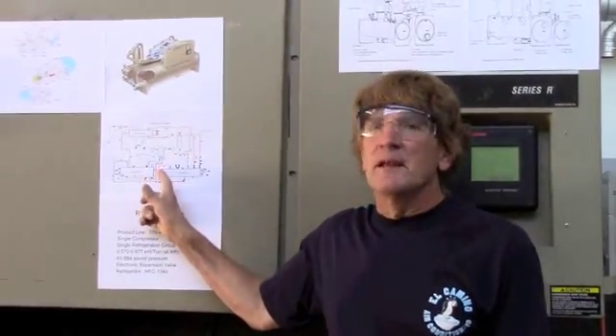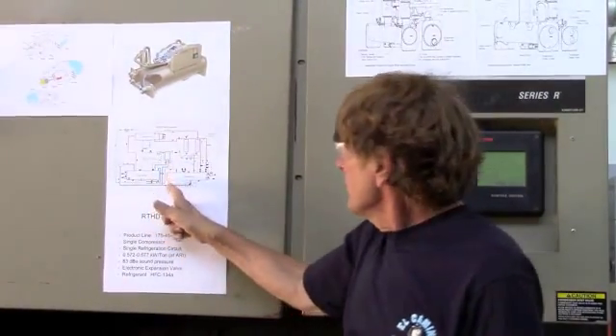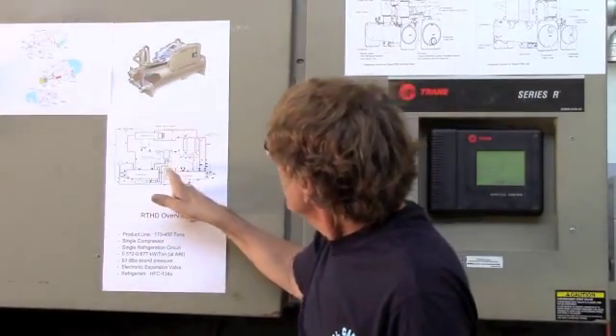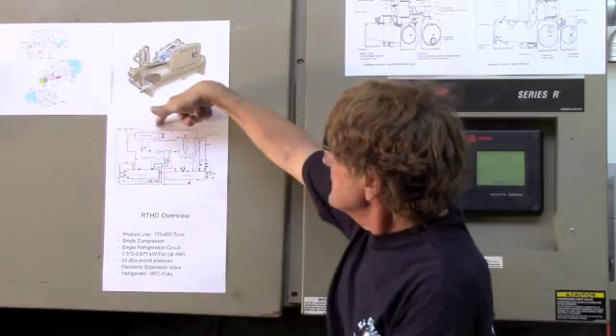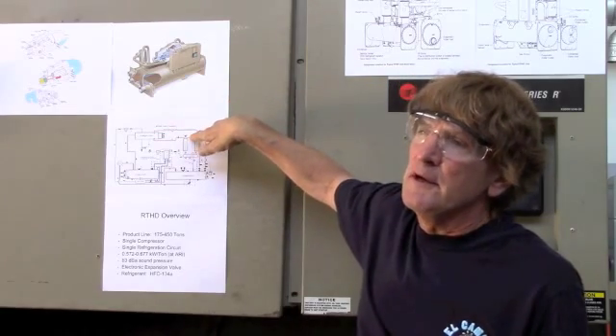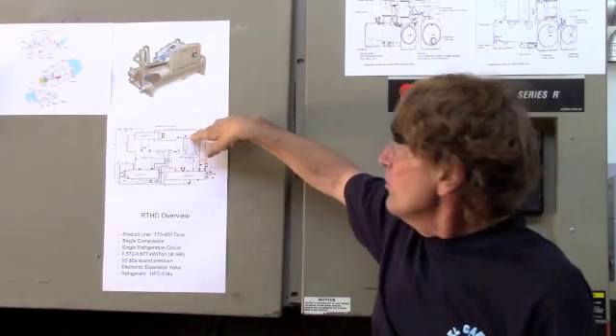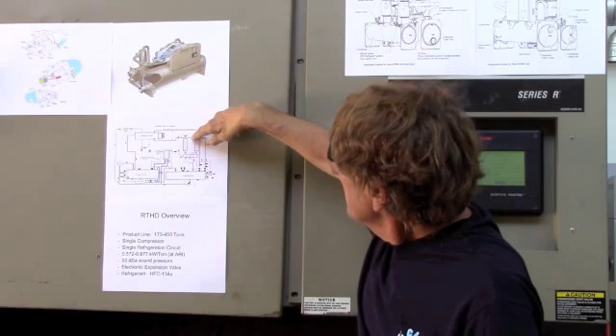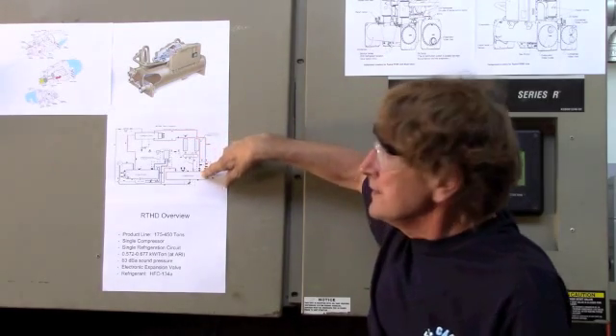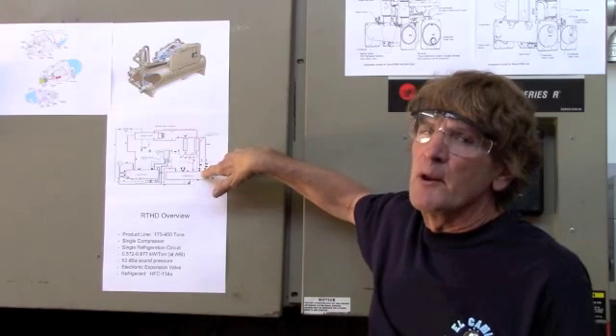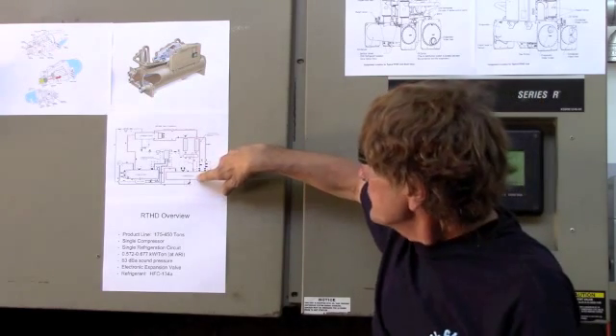In this particular case, it's a rotary chiller. We have the compressor section. Discharge gases, depending on what size, are going to go through an oil recovery process or oil separator. Out of the oil separator, it's going to go into the condenser, where we're going to run water through the condenser, cool off that refrigerant.